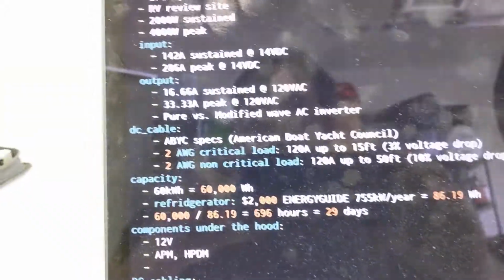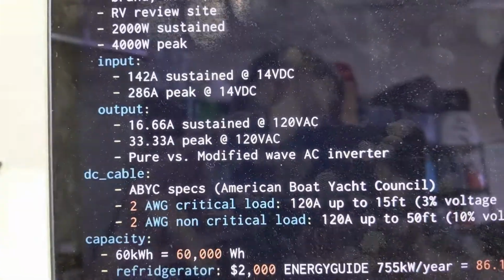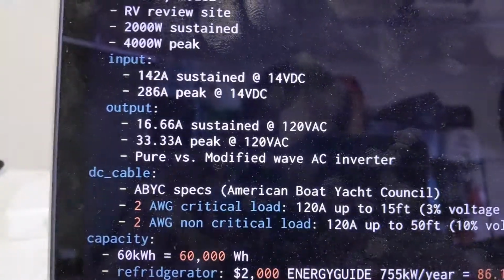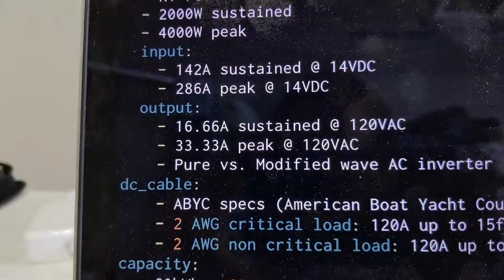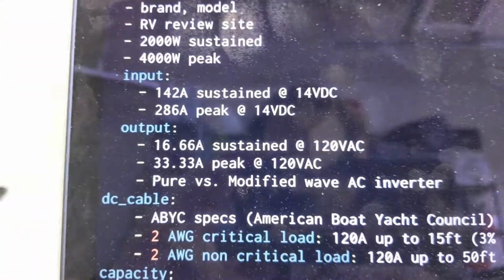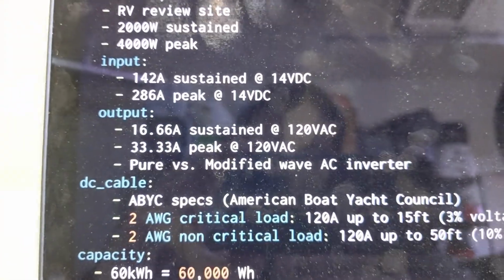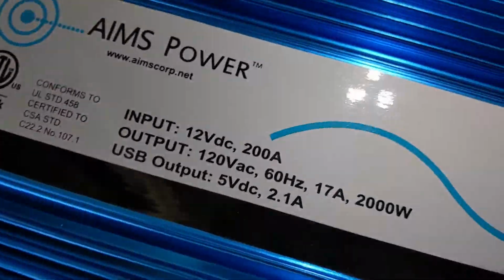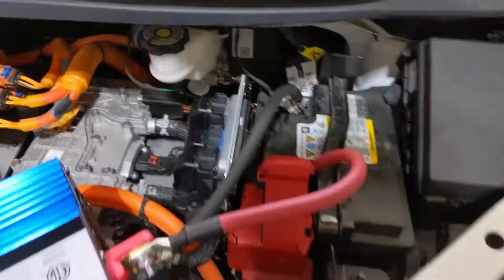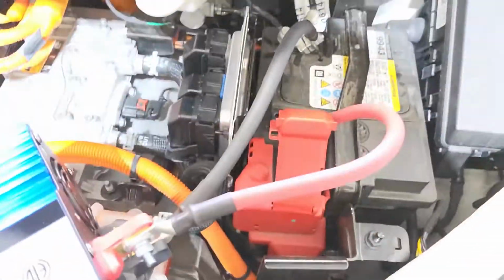So if we look at our output side, given the sustained 16.66 amps, which is the 2,000 watts sustained at 120 volts, it actually should say on here on the output side, 17 amps is our max. Yep. So given that we have a 100 amp limit on our cabling here on the DC side that we've set ourselves, we're not going to be able to pull that many amps.